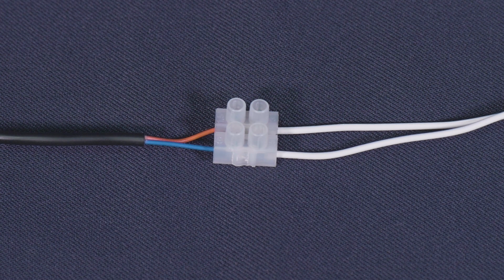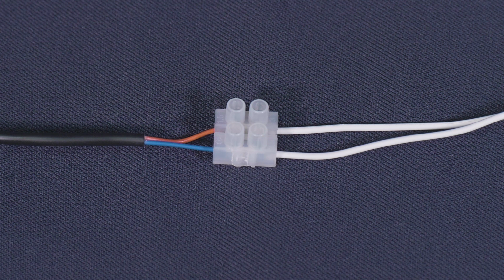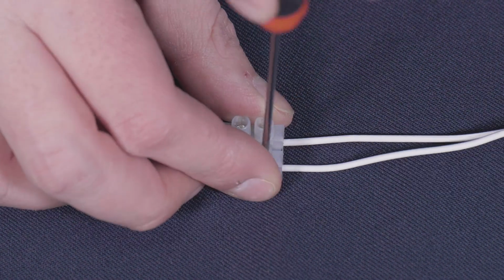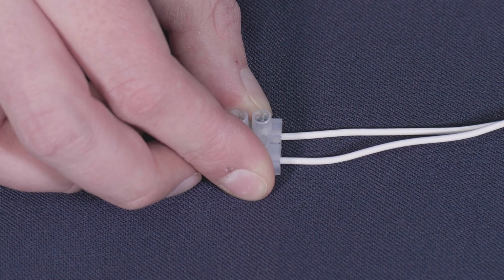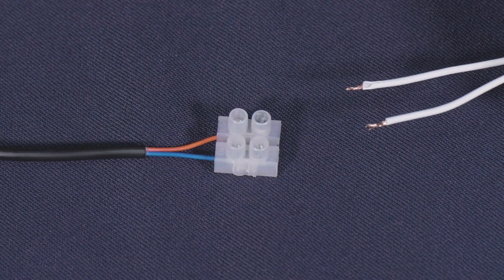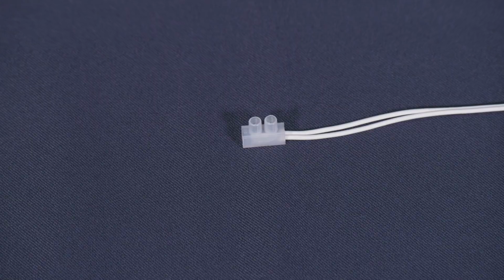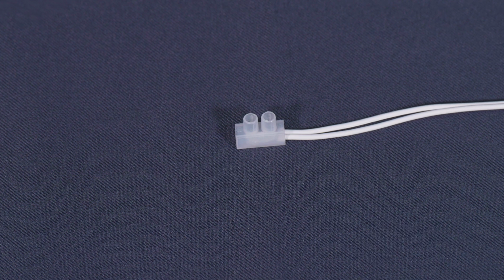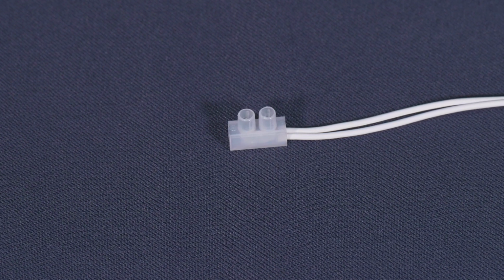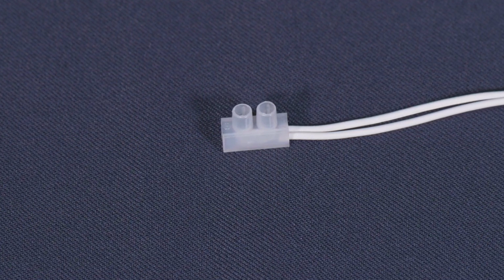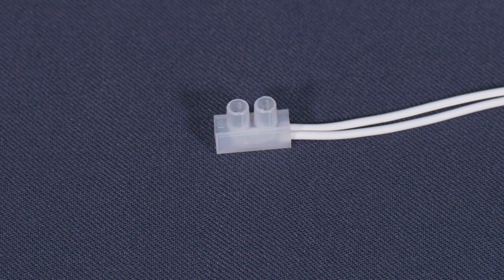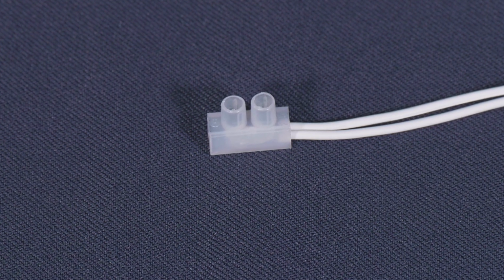To see where the issue lies, please disconnect the transformer bell wire from the connector block as shown. Once the bell wires are disconnected, wire the two bell wires together using a one-way terminal block like so. The pump should start after a short delay. If this is the case, then the flow switch may need to be cleaned out or replaced.